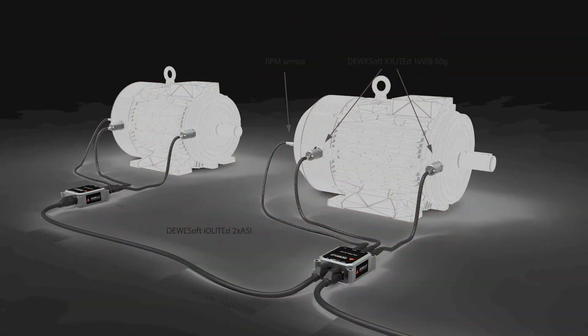Devices can be daisy-chained by a single cable for data, power, and synchronization. There can be up to 100 meters between the devices. EtherCAT protocol ensures perfect synchronization down to 1 microsecond, independent of cable length.